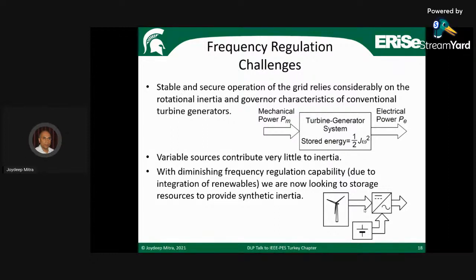But we don't notice these changes in frequency because there's so much inertia all over the grid from the conventional generators. But variable resources contribute very little to inertia, okay? You can imagine solar has no inertia at all, and wind, after filtering it out through the inverter through which it is connected to the grid, doesn't provide any inertia either. So now, with more and more wind and solar, the relative amount of inertia drops, and so the frequency regulation capability also drops.